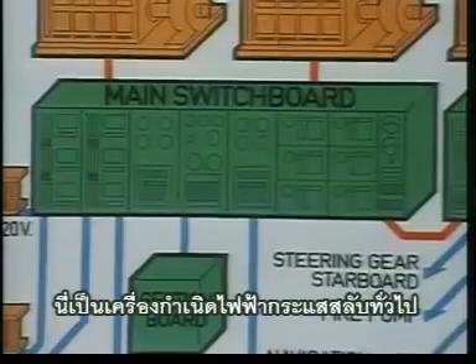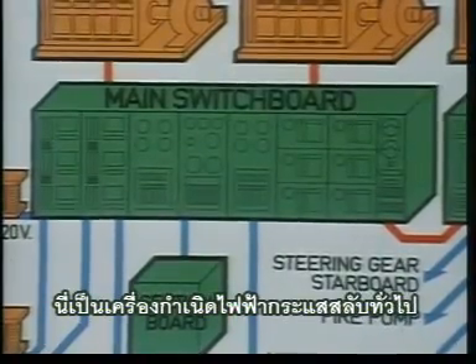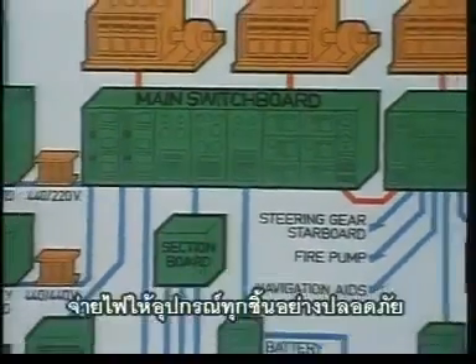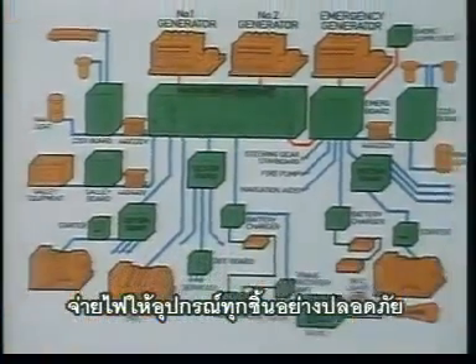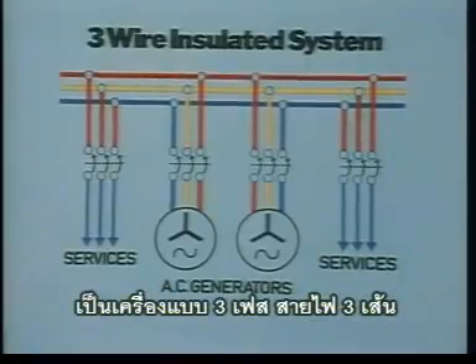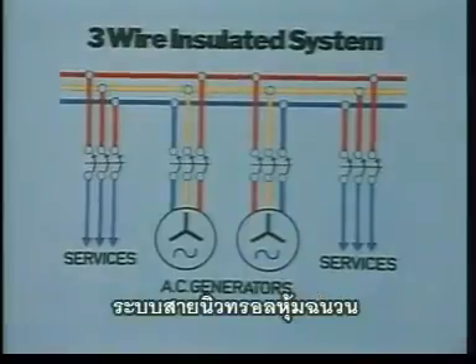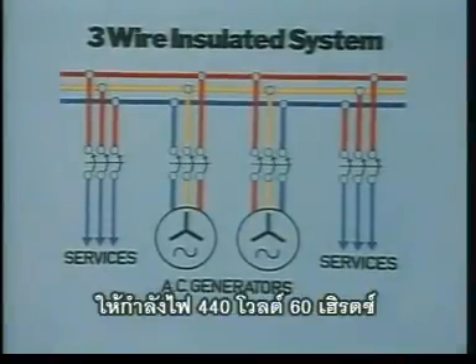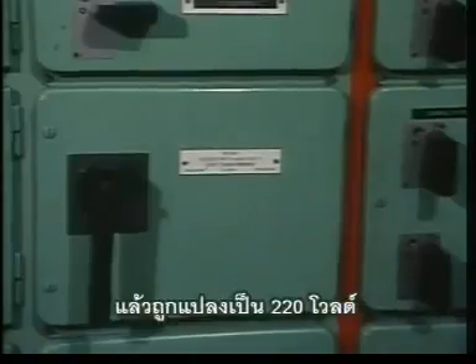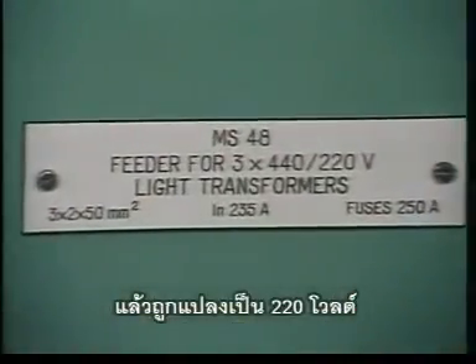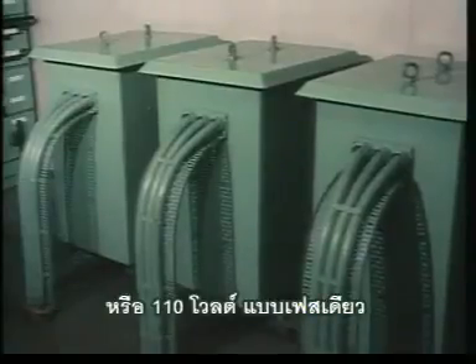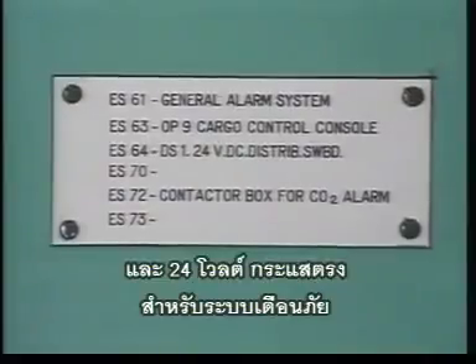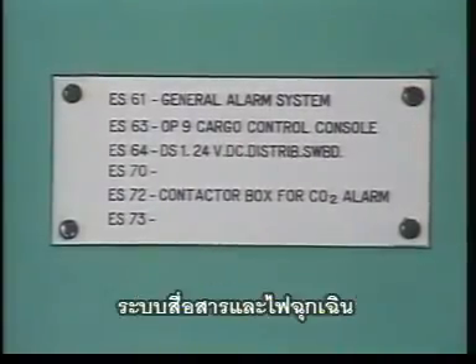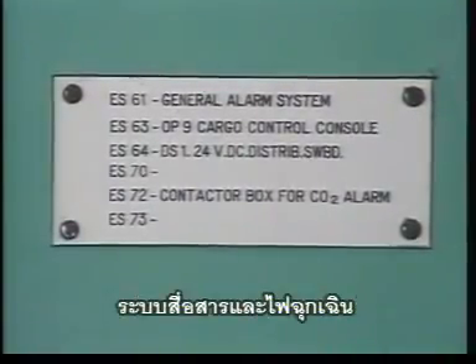This is a typical radial AC distribution system. Its basic function is to provide electricity safely to all loads. It is a 3-phase, 3-wire, insulated neutral system, providing power at 440 volts and 60 Hertz. This is then stepped down by transformers to 220-volt or 110-volt single-phase supply and a 24-volt DC supply for some alarms, communication and emergency lighting.